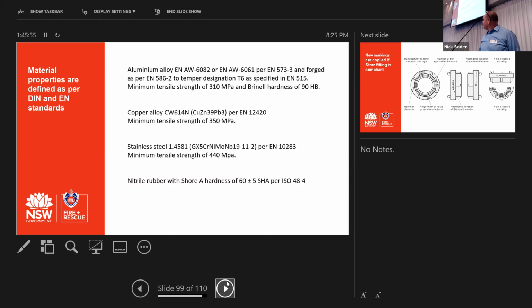Material properties are now defined. It's quite technical. I'm not going to go through all of these, but generally, we know some other fire jurisdictions are actually sending Storz away for independent materiality tests, and they're actually producing lists of compliant and non-compliant Storz. We haven't done that in New South Wales yet, but we may particularly do that in the future. So you can see there's EN standards for the material, EN standards for the forging process, and EN standard for the temper designation. If you meet all those European standards, we know that Storz is going to perform as we require for firefighting.